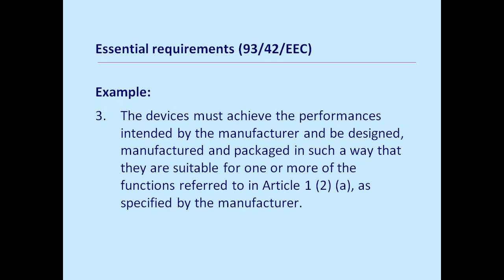I've been talking about essential requirements as well, that medical devices have to conform to in the Medical Devices Directive. Here's just an example of one essential requirement from the directive. The devices must achieve the performances intended by the manufacturer and be designed, manufactured and packaged in such a way that they are suitable for one or more of the functions referred to in the definition of a medical device. So the device only has to do what the manufacturer says it does. It doesn't have to meet a particular level of performance or be effective in a particular area. It just has to do what the manufacturer says it does.